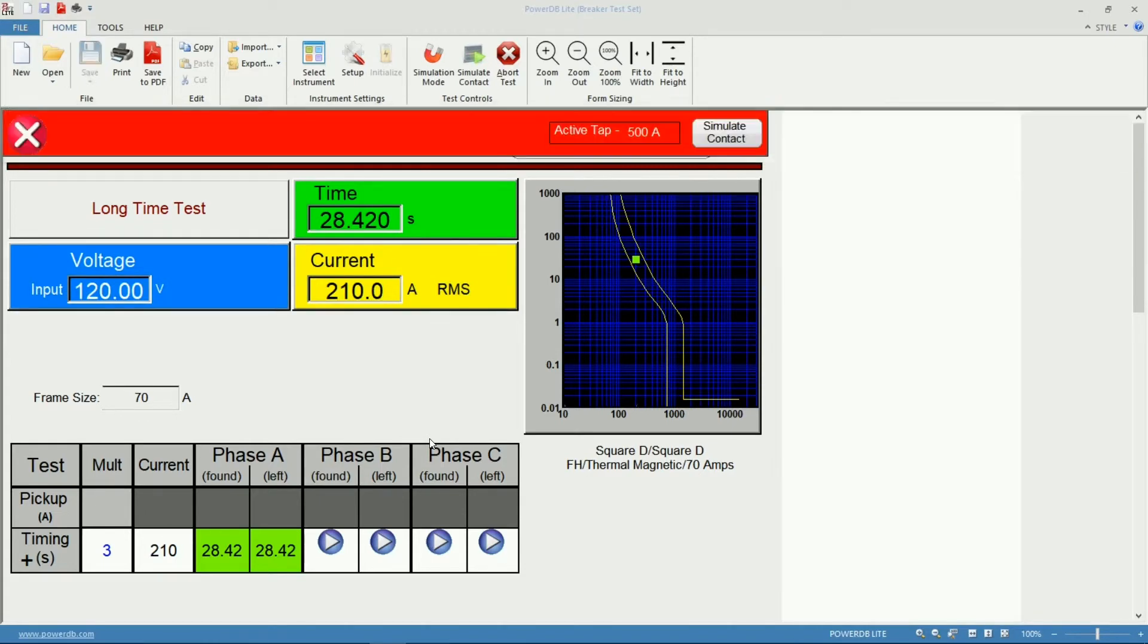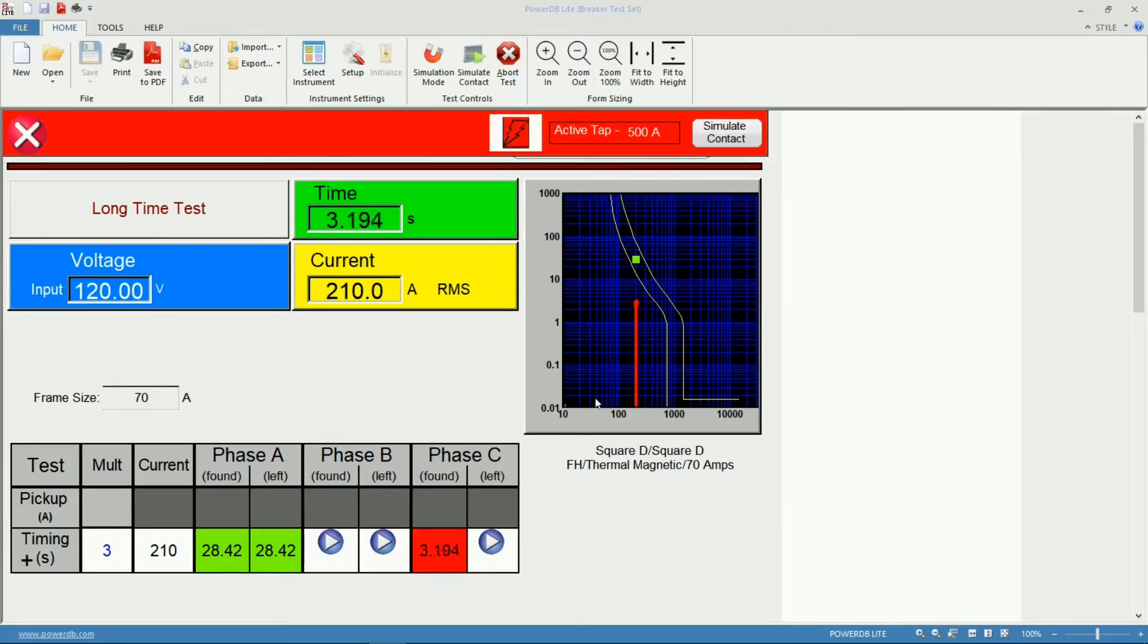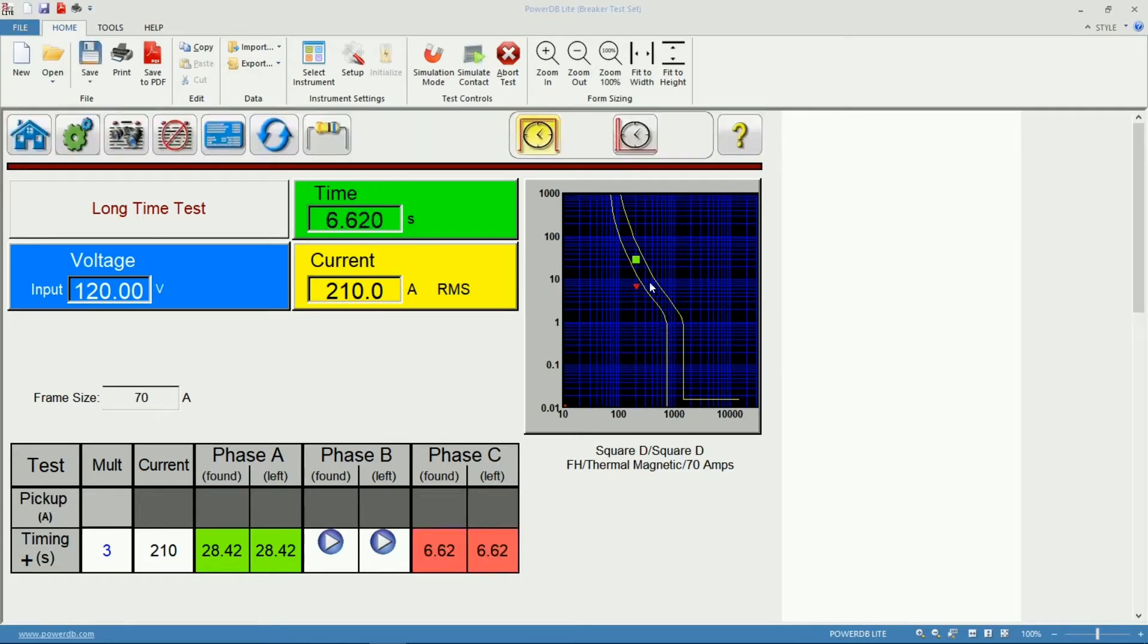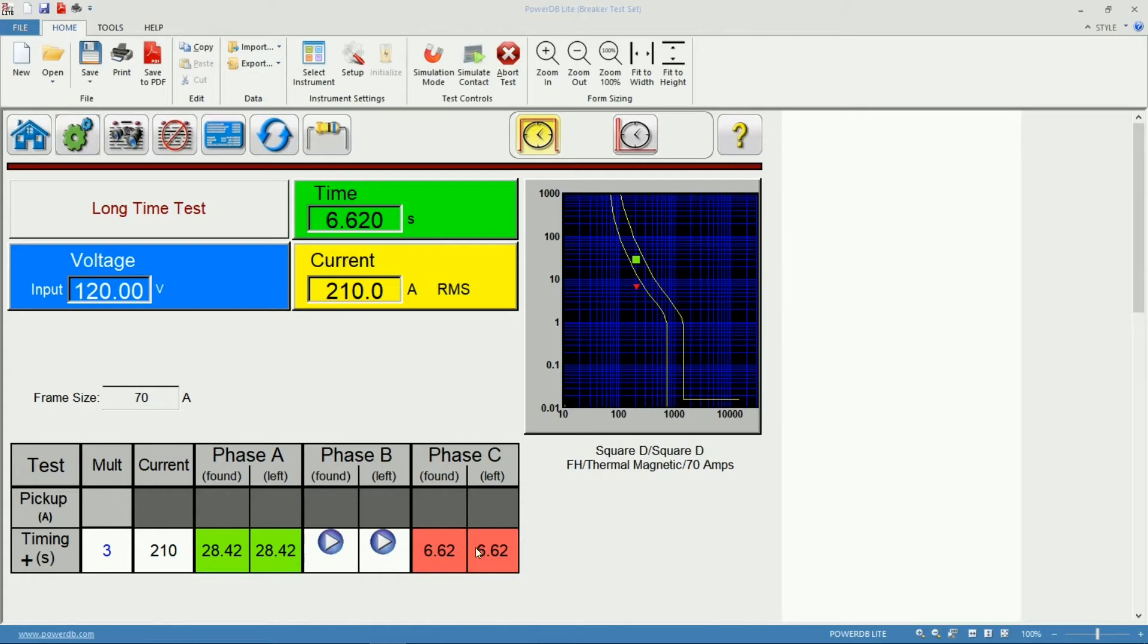Same process, it will find the TAP, calculate the impedance and start the test. In this case I'm going to simulate a trip outside the limits so we know how that looks in the report. Right here on my testing screen, both of my results are red.